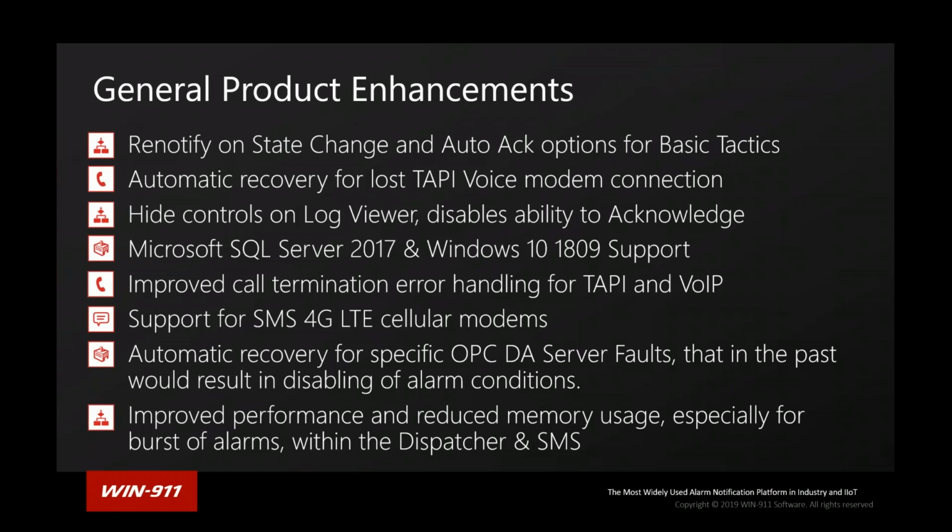Where you can run into a problem is if we get a bad quality event, but we also get an OPC DA server fault along with it. A good example of this is if you define the tag or item incorrectly. In our software, it's written down one way, but that does not exist in the OPC server. You will get a bad quality update for that, but it'll also mention something along the lines of this tag does not exist. Now, instead of us trying to keep connecting to this tag, we just drop the handle for that item and ignore it. A lot of OPC server faults are not recoverable, and so this is normally how those are handled.